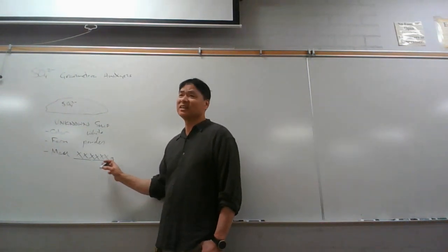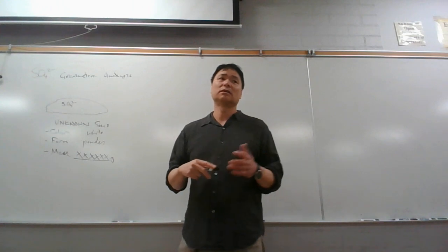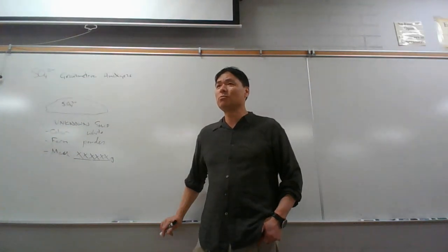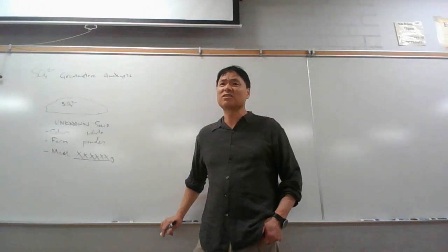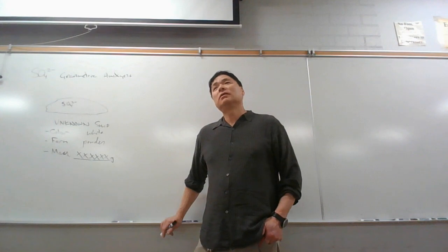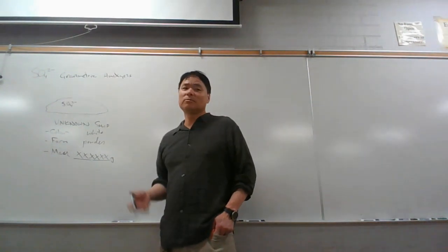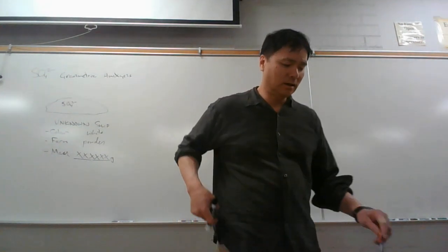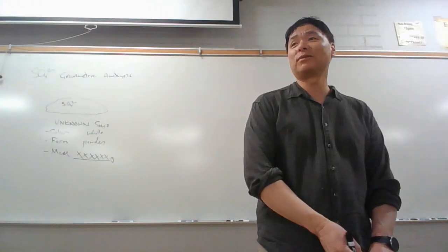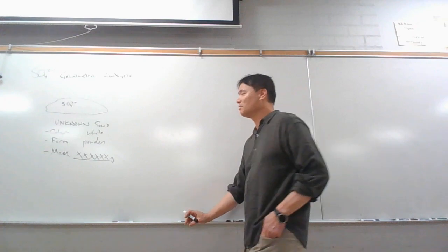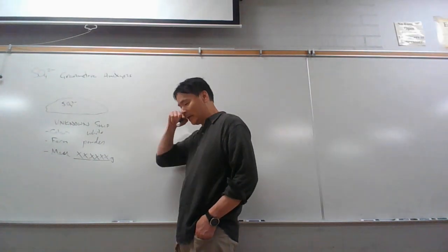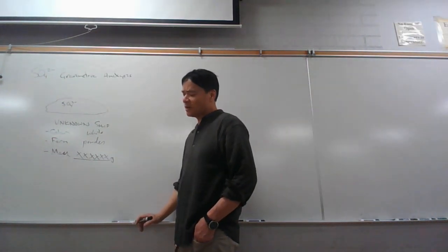Although this is the highest precision, do we know it's accurate? No. We don't know it's accurate until we do what? We need to do what step to make sure it's reading accurately? You gotta tare it, you gotta zero it out. Well, even if we tare it, it still might not be reading accurately. We gotta calibrate it, right? And we calibrate it with what are called standard masses. And we buy these standard masses. You could buy very expensive standard masses.